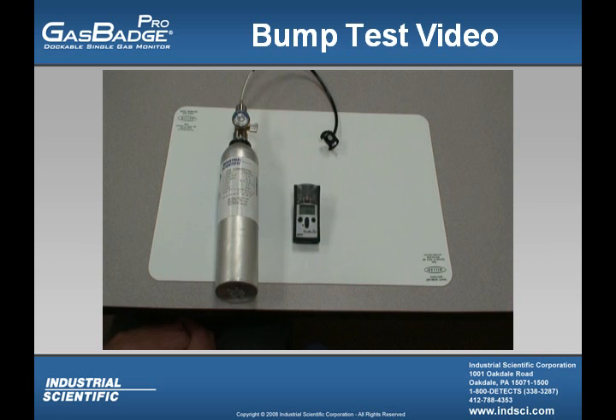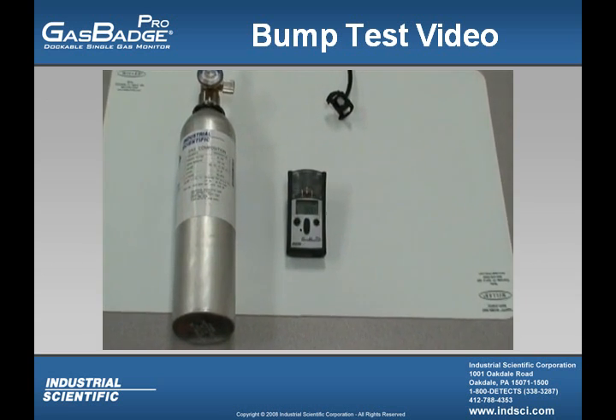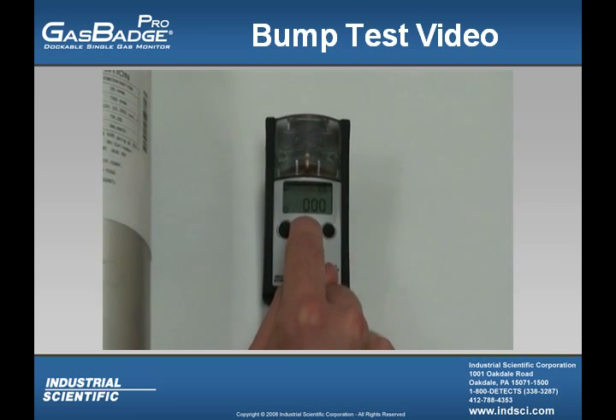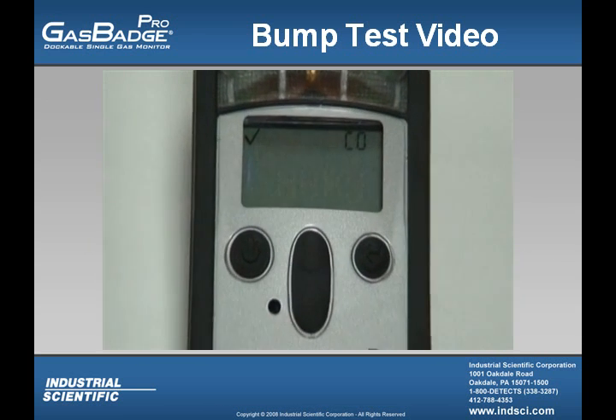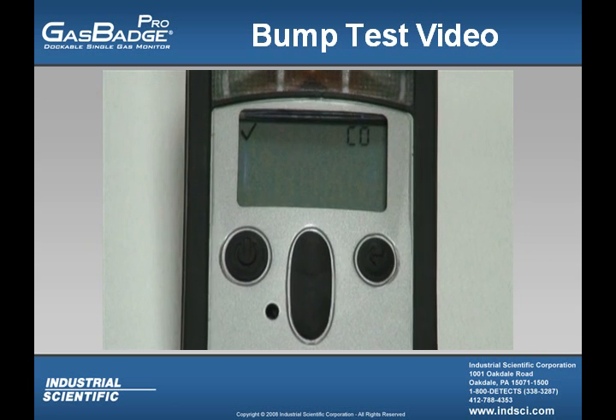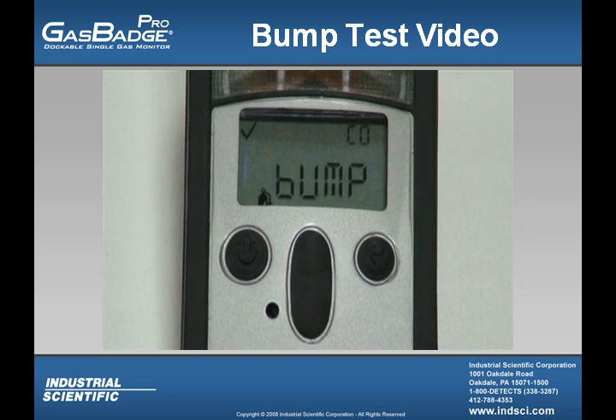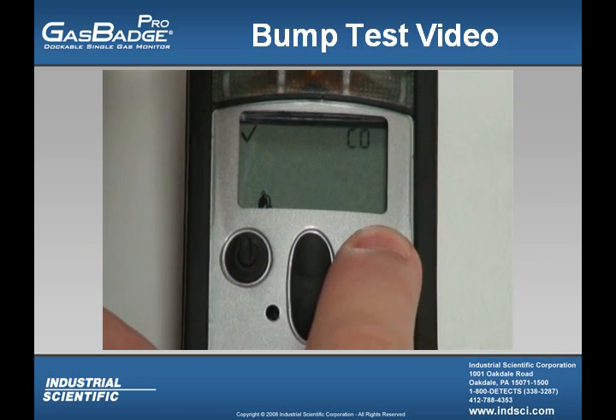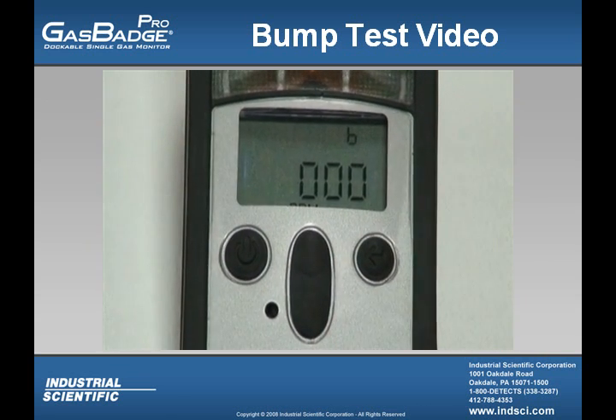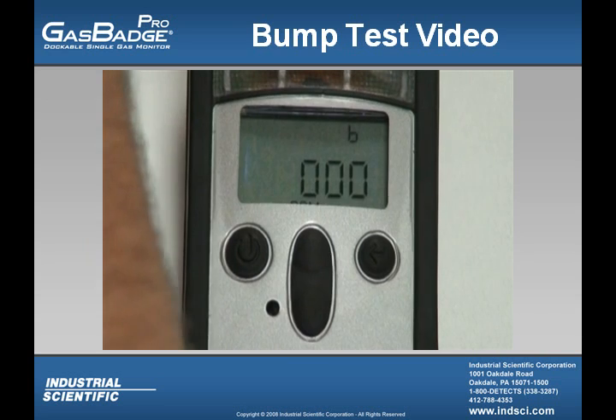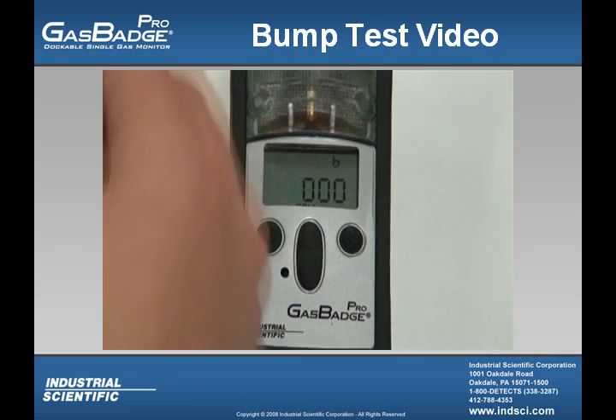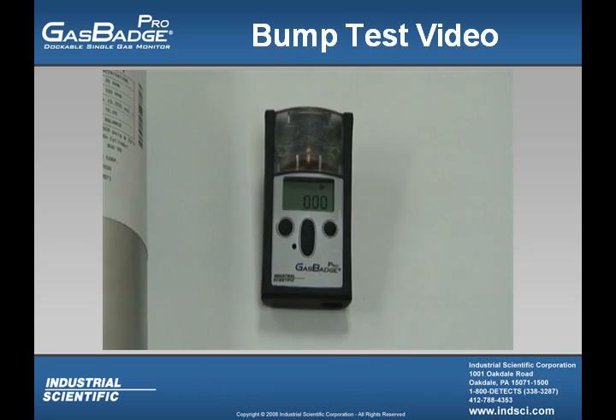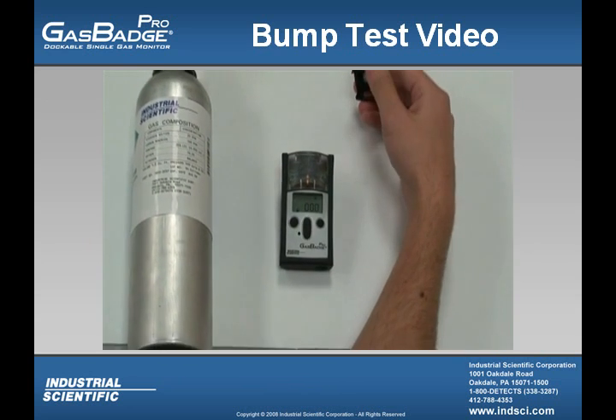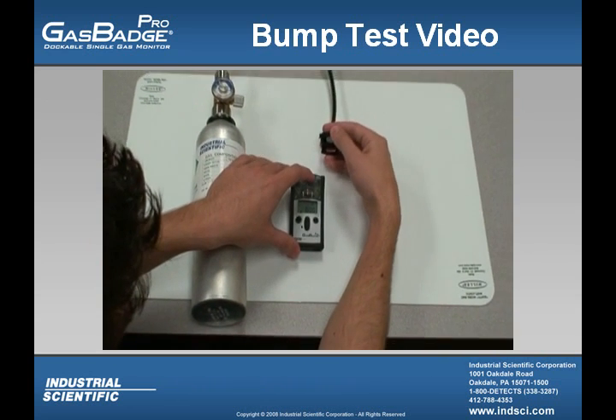Let's take a look at how to bump test the instrument using the menu version. What you want to do is press the up button 2 times. Press the up button once, and you'll see the 0 with a slash through it blinking. Press the up button again, and you'll see the word bump flashing. From here, you're going to want to press the enter button. You'll see the letter B in the upper right hand corner, and the calibration gas icon flashing in the lower left hand corner. You're going to want to open up the regulator on the bottle, and then apply your cal cup.